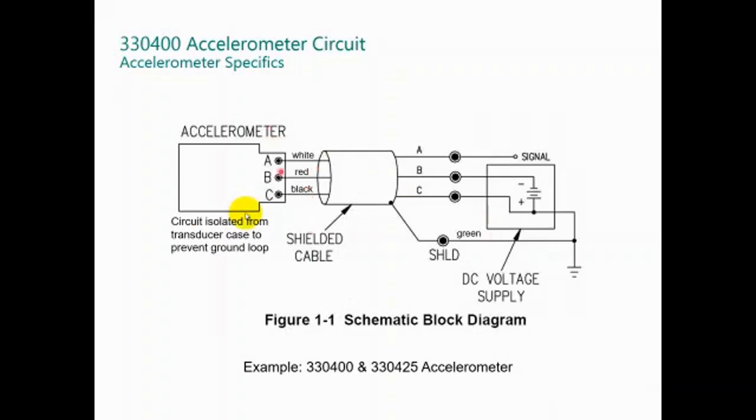The accelerometer has three wires: white, red, and black. Remember, red is power, white is signal common, and the black is common. You can connect it here to test using a power supply. You need to provide power, and then using this white and black to check the signal. Provide the power between the terminals, red and black.